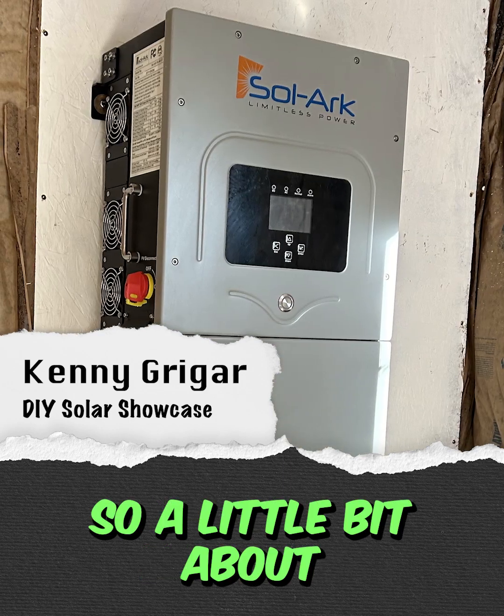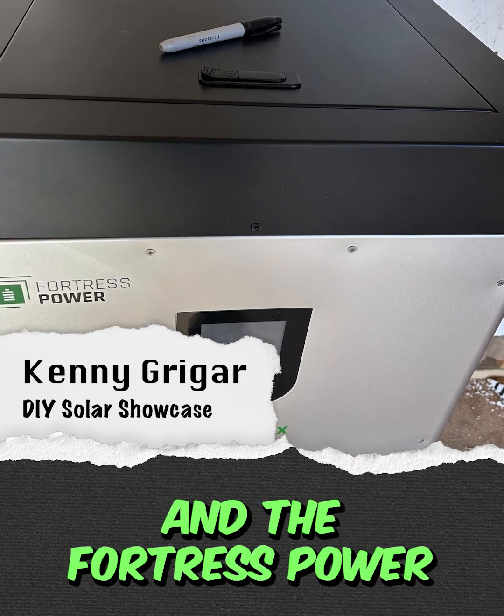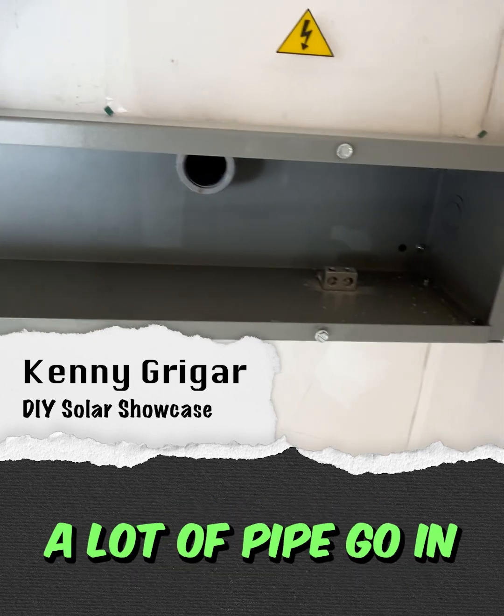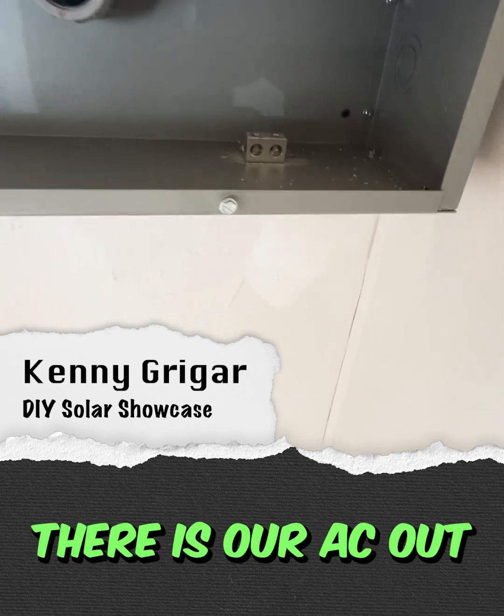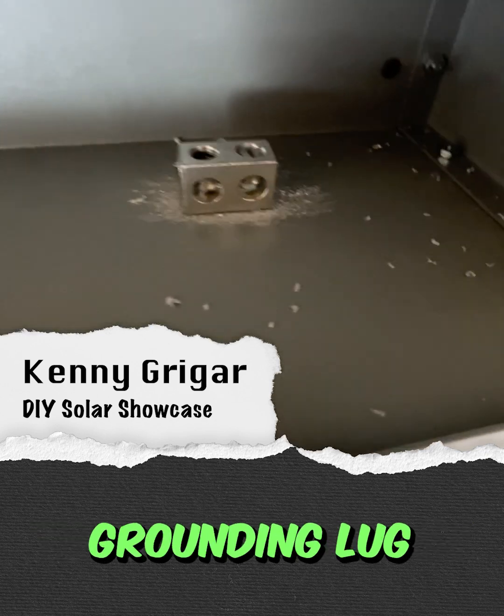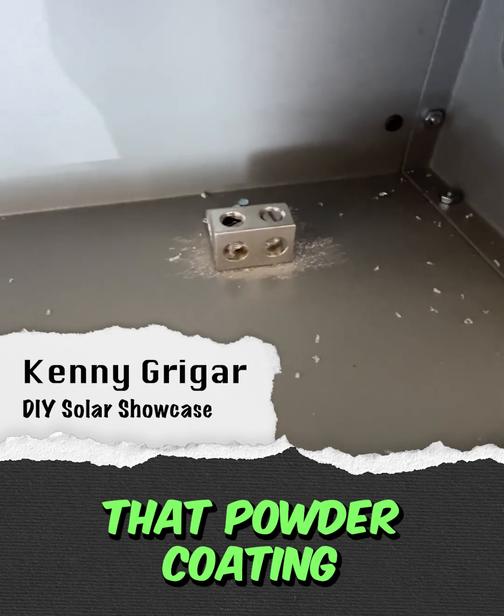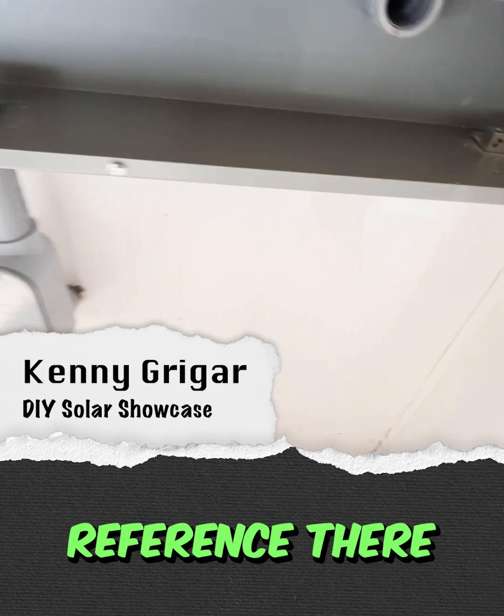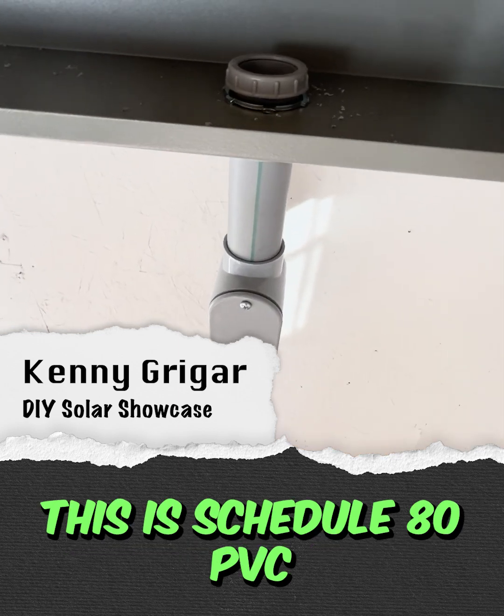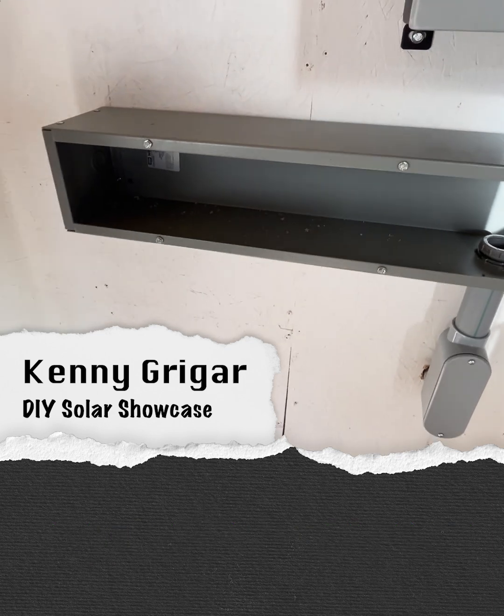A little bit about the Sol-Ark install here and the Fortress Power setup. Instead of having a lot of pipe go in, we're going to put a gutter. That right there is our AC out. We have our grounding lug — notice the scratching behind that. You want to take off that powder coating to make sure you've got a good grounding reference there. This is schedule 80 PVC, and the rest of it will be in metallic conduit.